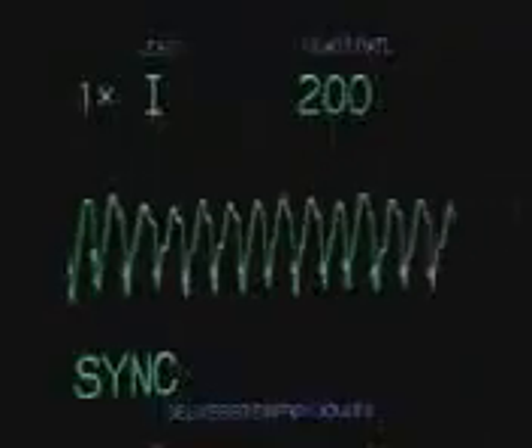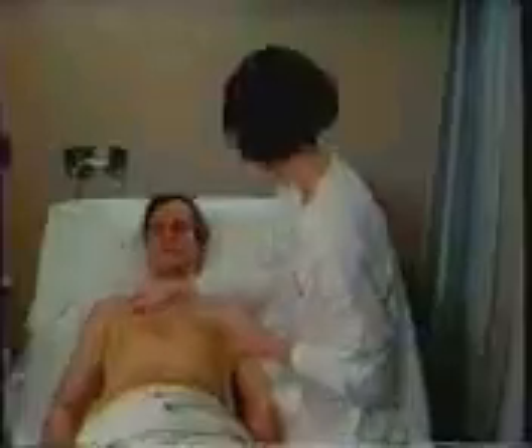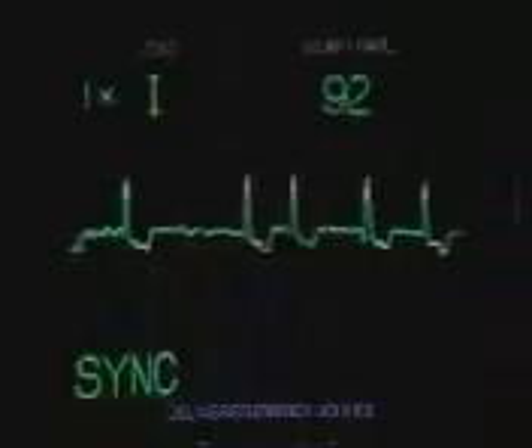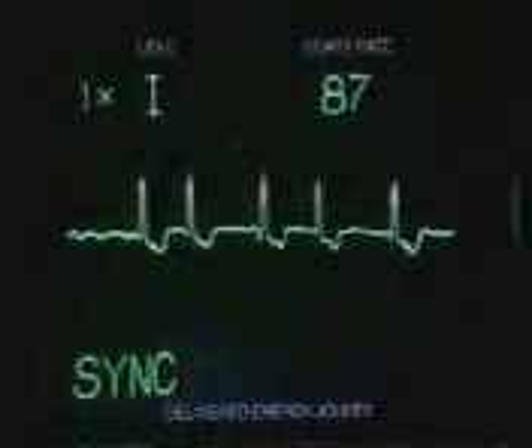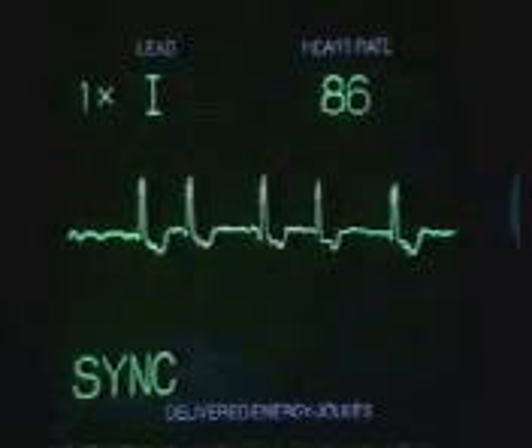For certain arrhythmias, such as VTAC or atrial flutter, synchronized cardioversion is indicated. Connect the ECG leads to the patient and the PD. You cannot use paddles for the ECG source when performing synchronized cardioversion. Select Monitor On. Press the Sync button on the front panel. Verify the R wave is being marked on each beat. This appears as an intensified dot or dash on the monitor.